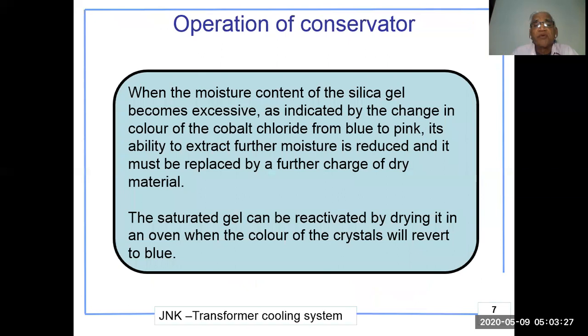When the moisture content of the silica gel becomes excessive — as indicated by the change in color of the cobalt chloride from blue to pink — its ability to extract further moisture is reduced and it must be replaced with a fresh charge of dry material. The saturated gel can be reactivated by drying it in an oven, after which the color of the crystals will revert to blue.